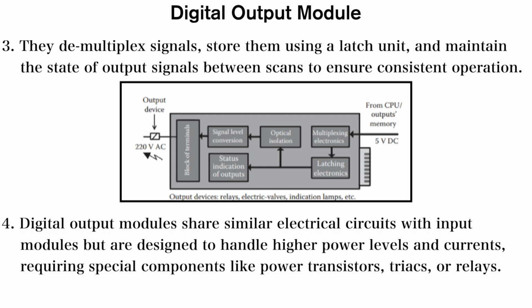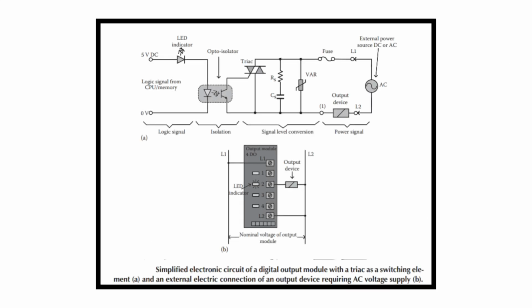The digital output modules share similar electrical circuits with input modules but are designed to handle high power levels and currents, and require special components, which include power transistors, triac circuits, or relay circuits. These components can generate electrical and magnetic noise, so manufacturers have to keep this in mind and use surge suppressors, varistors, and fuses to protect the whole circuitry. The output devices controlled by digital output modules include power relays, solenoids, indicator lights, alarm devices, and electronic devices which often need an on-off state change or a toggle change. External power sources are necessary for digital output modules to supply power to the output devices.